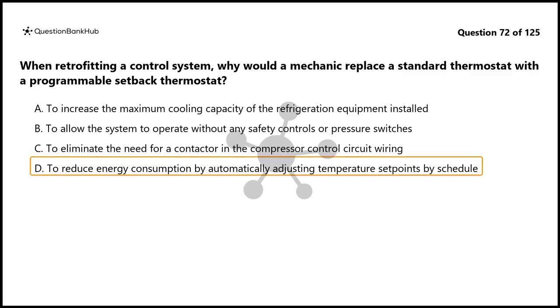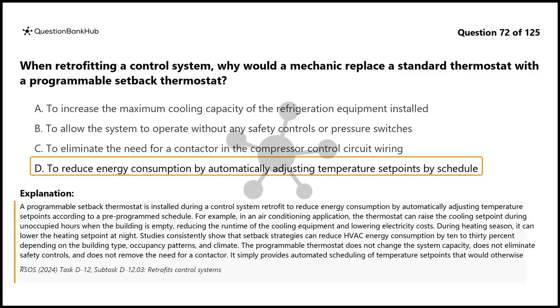The correct answer is D. A programmable setback thermostat is installed during a control system retrofit to reduce energy consumption by automatically adjusting temperature setpoints according to a pre-programmed schedule. For example, in an air conditioning application, the thermostat can raise the cooling setpoint during unoccupied hours when the building is empty, reducing the runtime of the cooling equipment and lowering electricity costs.